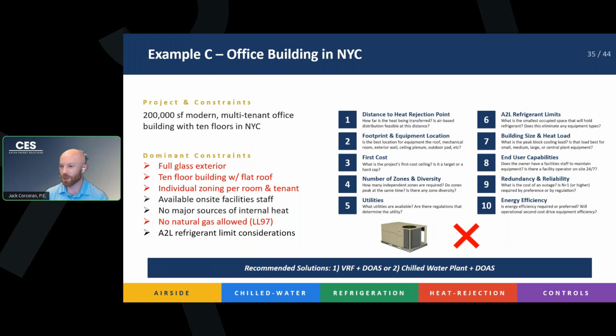minimal refrigerant piping shafts, right? We don't have these huge ducts traversing the building. But our last consideration point is the A2L refrigerant limit. So while we have many ways to combat that with easy mitigation strategies, and if you're looking for more information on that, we're happy to help, the landlord maybe doesn't want to do that. So chilled water or condenser water is probably it, with a separate DOAS system. That way you're running water throughout your building, not refrigerant or ductwork.